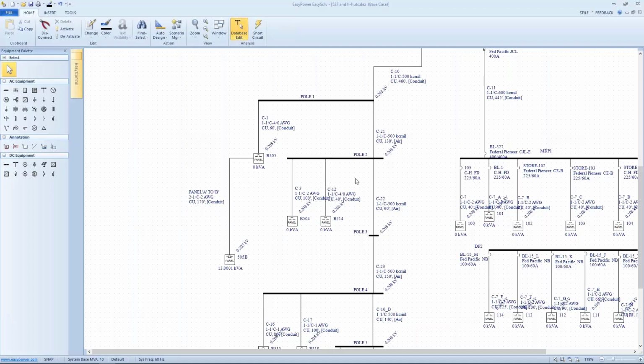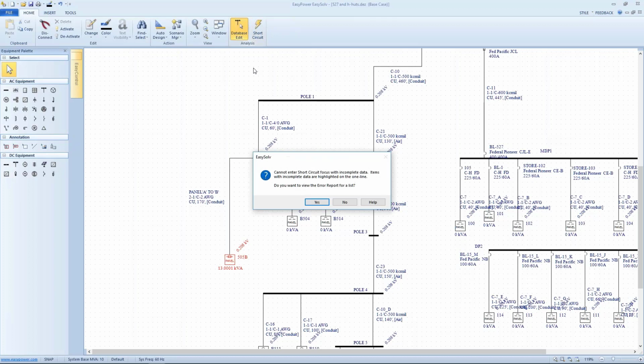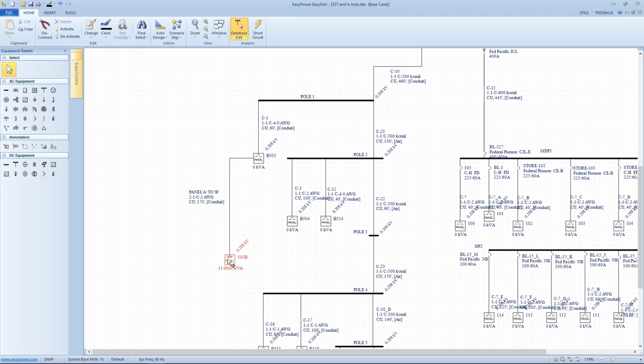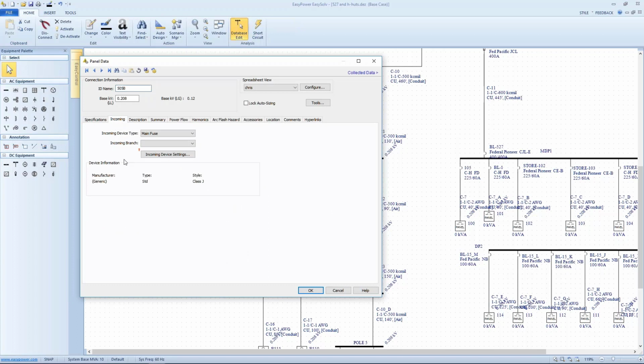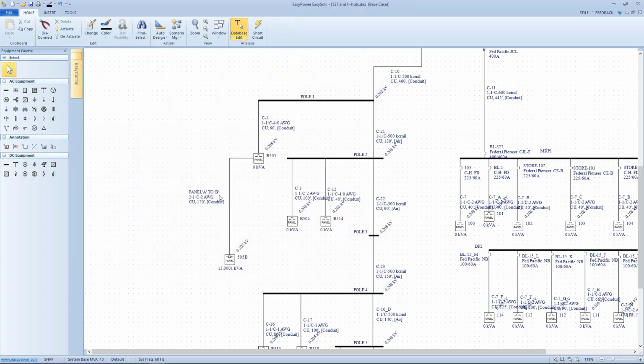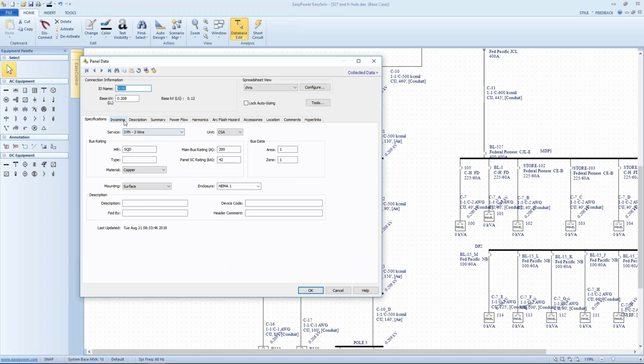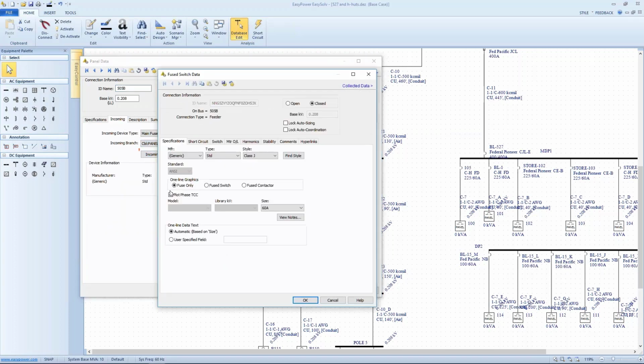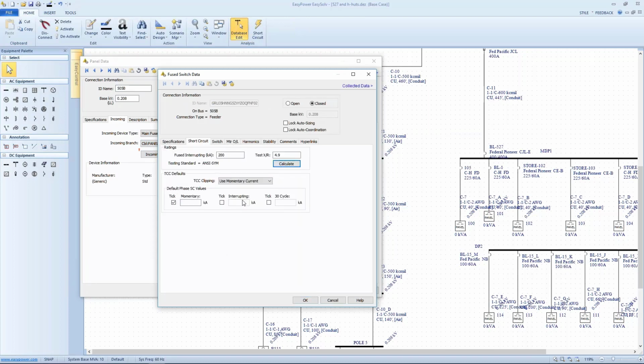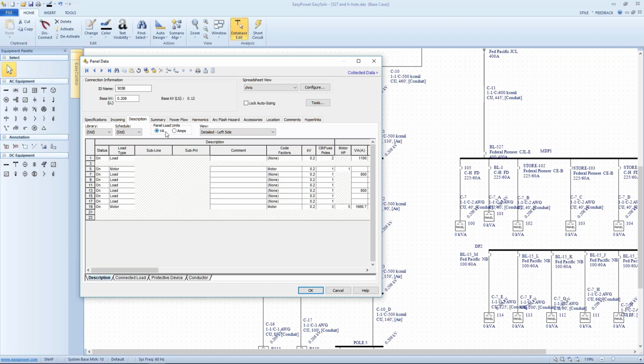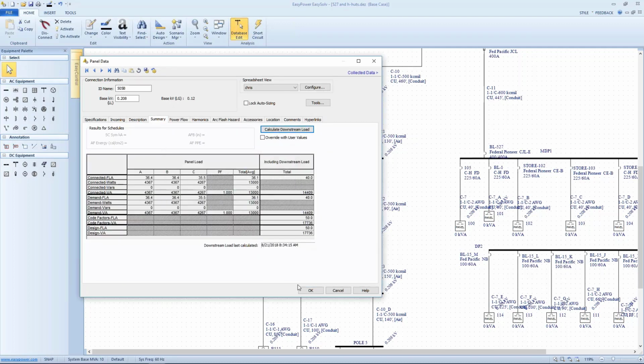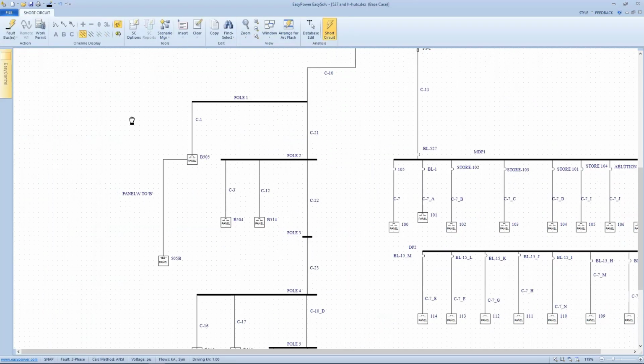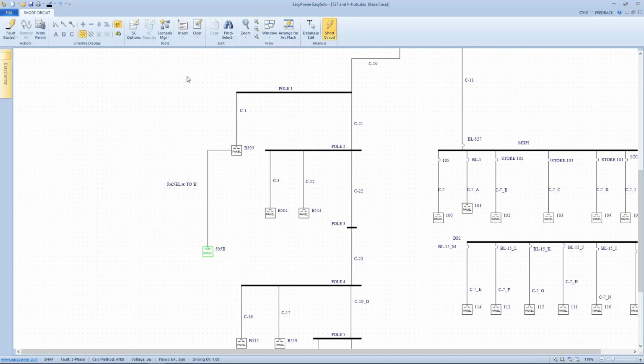And to my point, here we're going to go to short circuit focus, and I guess I didn't do this one. What I didn't do was tell it which cable we have coming in. So let's try that again. Incoming 60 amp. All right, we're in short circuit focus. We're going to fault this particular bus, and we're going to look at incident energy.